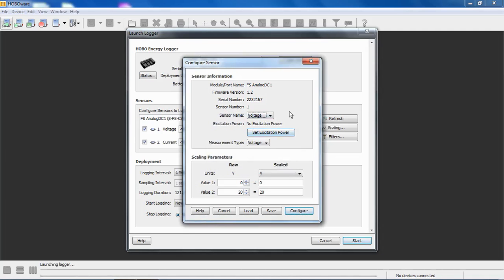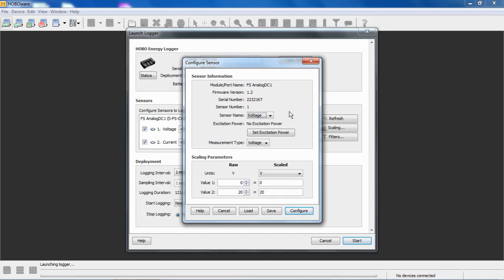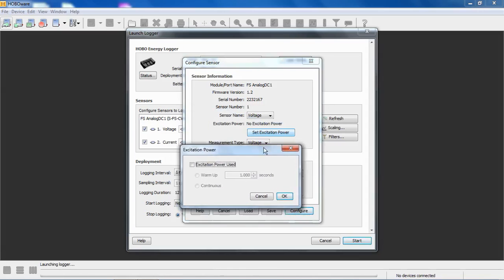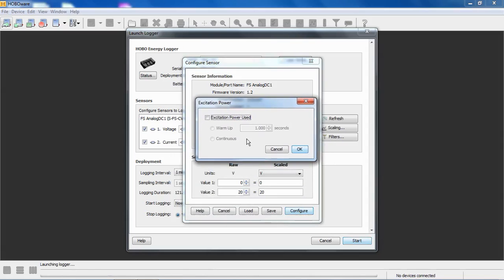Below that is where we can turn on excitation power. The CVIA module can provide 12-volt excitation to your sensors that require excitation to a maximum of 200 milliamps, and the 200 milliamp limitation is across the entire logger. So if you had six analog channels or three analog modules installed, the total excitation current cannot exceed 200 milliamps for the whole logger. To configure excitation power, we would click on, set excitation power, and then check off excitation power used to enable it.